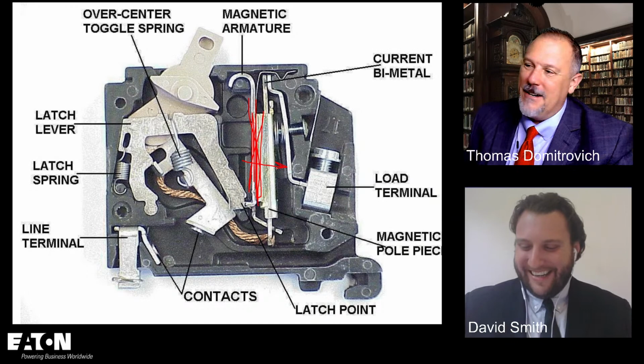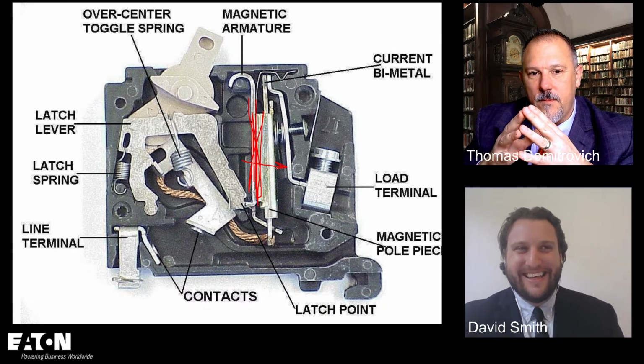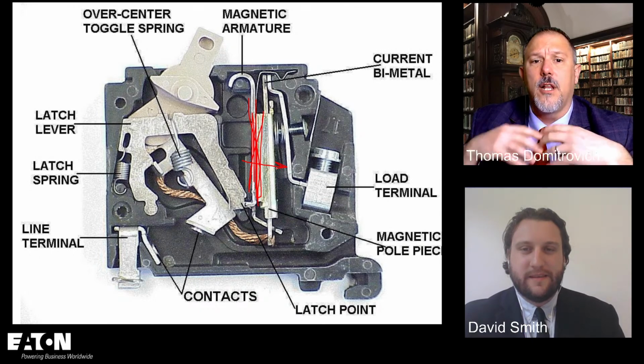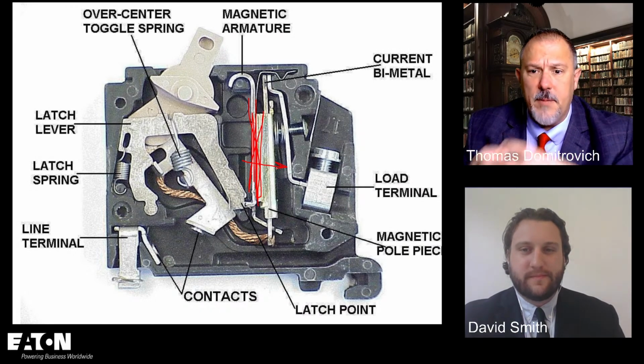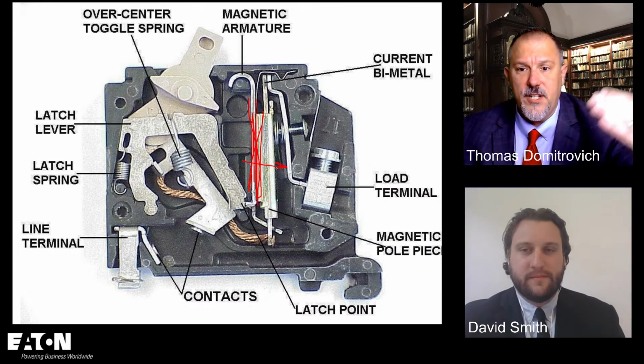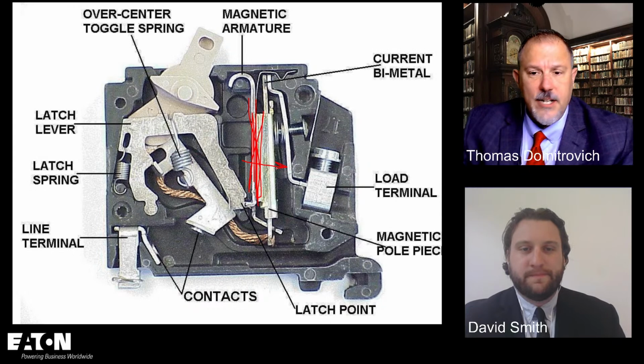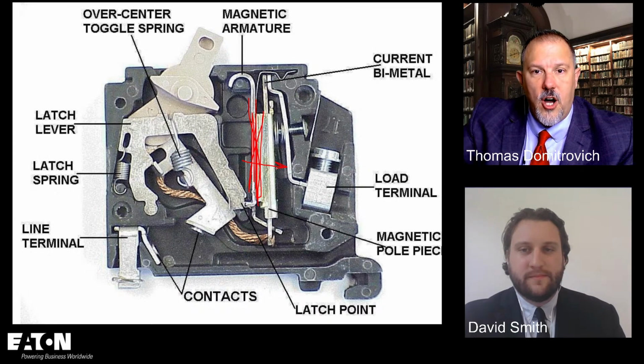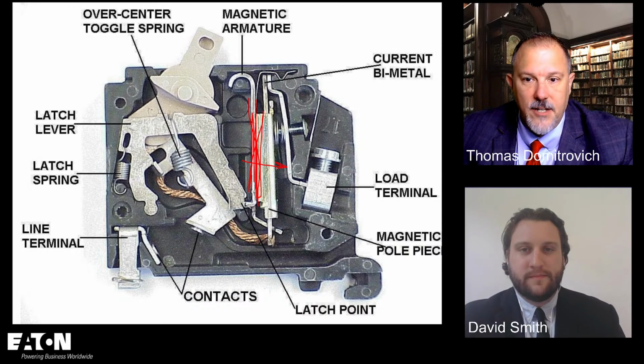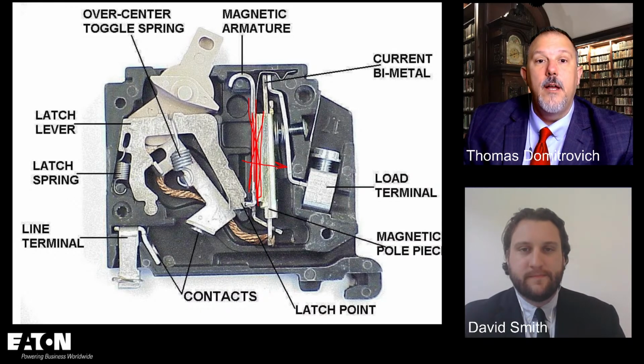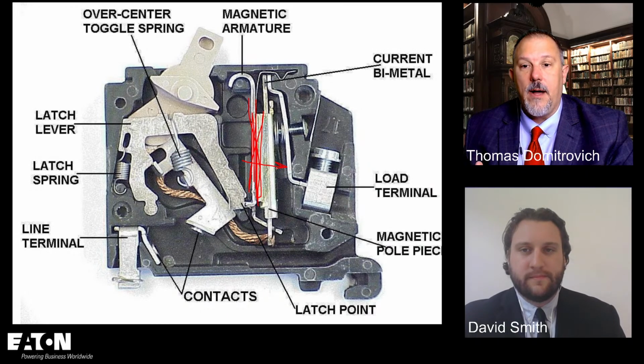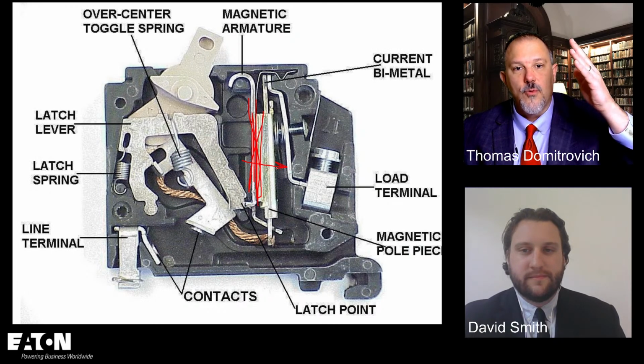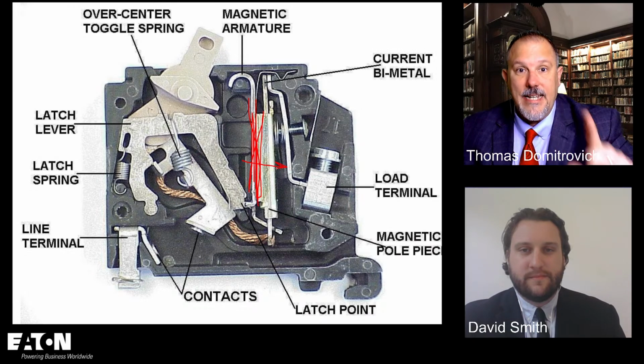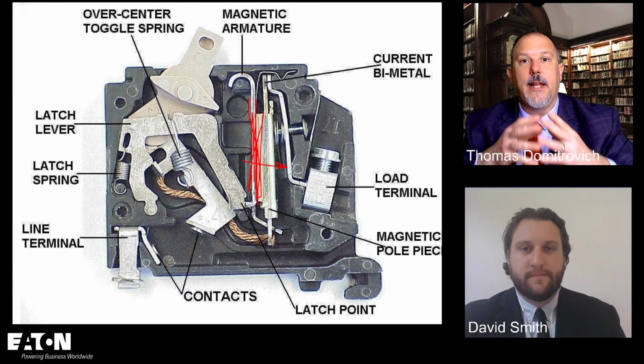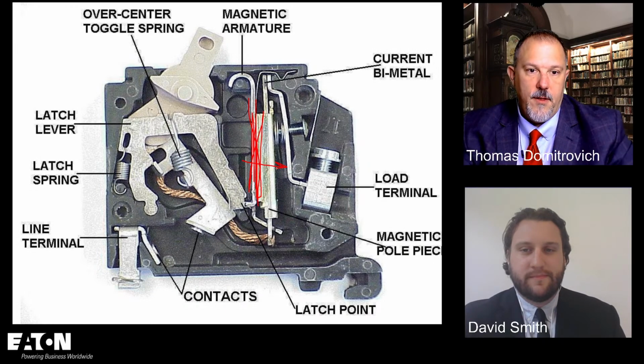Don't hold back. So this device needs a lot of current, and it needs to be persistent for me to generate heat. If I had an electric stove and I turned my burner on and off, on and off, I could put my hand on it and not get burned. But if I turn it on and let it heat up, now I'm going to generate heat. So what happens during an arcing event is I'm not drawing enough current through that bimetal to heat it so it bends, and I'm not generating enough magnetic force to drop that latch.